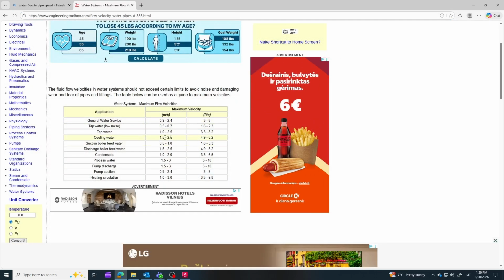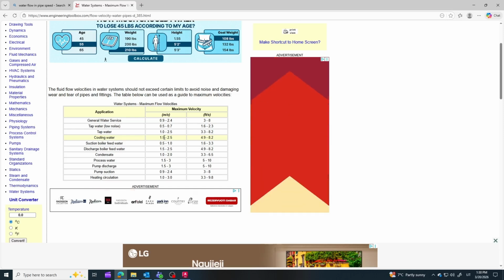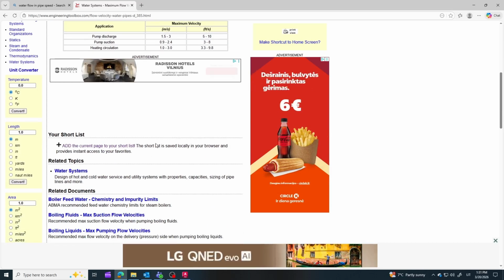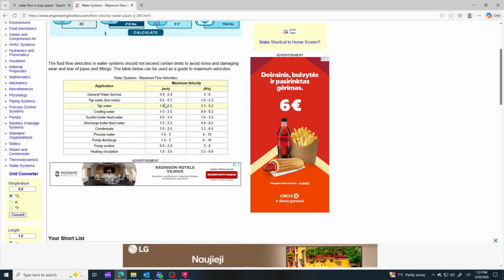Here you can see recommended velocity ranges depending on application. For example, cooling water systems usually operate around 1.5 to 2.5 meters per second. This is exactly the range we're targeting for our chilled water system. We detail the chiller connecting pipelines using this table as a reference. We can check whether our piping design makes sense.